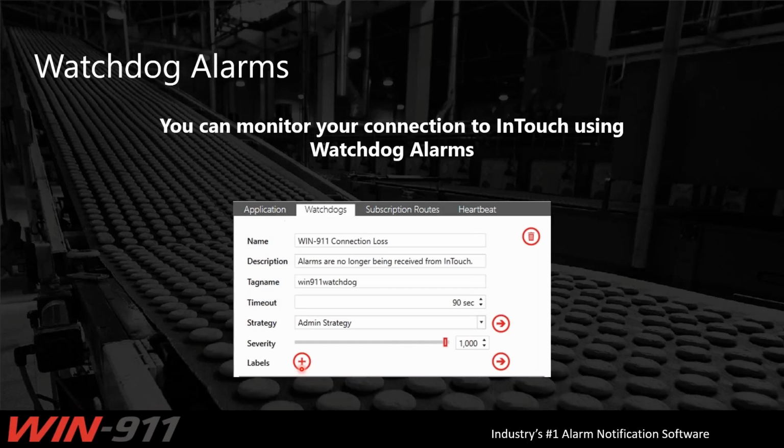But yeah, best practice there is usually an alarm that's basically going active, inactive all day long. You could filter it out of your alarm summary screen in InTouch, so you don't have to keep seeing it there. But as long as we keep seeing that state change, we'll think that everything's going fine, and you won't get your watchdog alarm. However, if the alarm stopped processing and we did not see that state change, after 90 seconds in this case, we would send out a notification saying, hey, looks like something's wrong. We're not receiving alarms from InTouch, and you can go take a look at it.